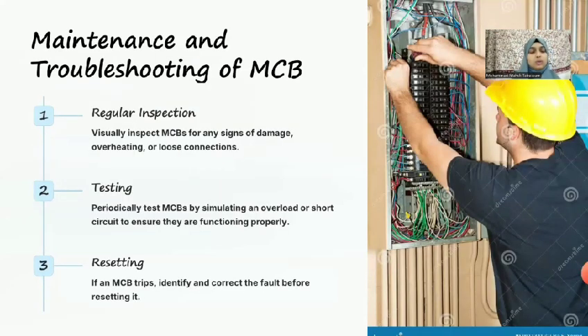What is the maintenance? How to maintain or troubleshoot the MCB? By regular inspection, like visually inspecting the MCBs for any signs of damage or overheating or loose connections. We have to regularly check them, and we can maintain the MCB by that. Testing: by testing it periodically for a fixed time, we have to check whether the MCB has an overload or some short circuit, so that it can function properly. Resetting: if an MCB trips, identify and correct the fault before resetting it.